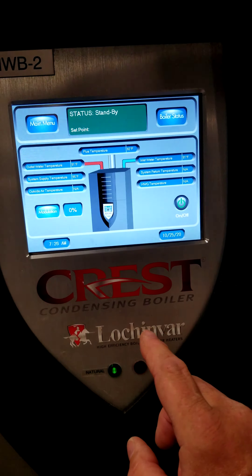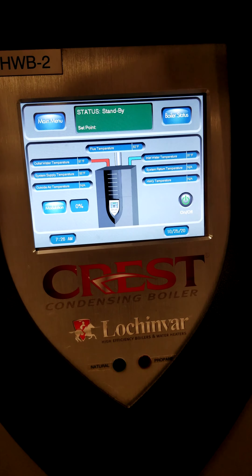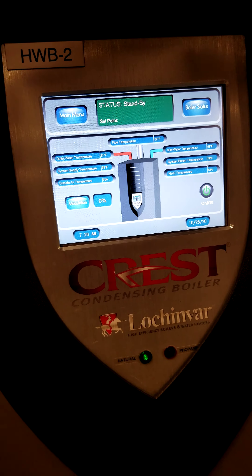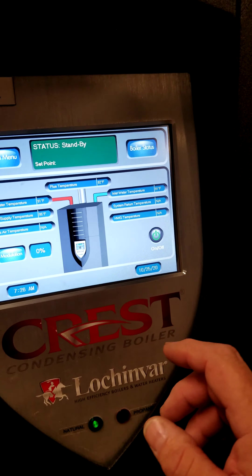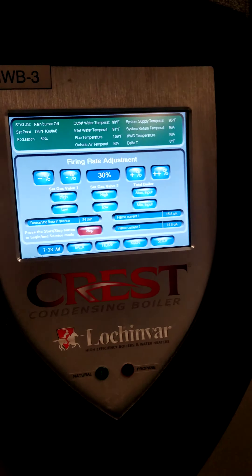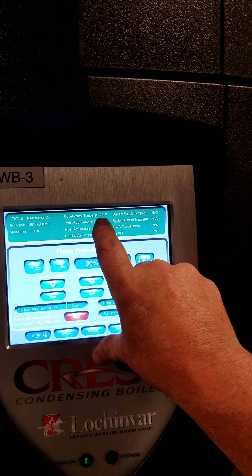Numbers one and two are going to try to start but they're going to fail because their blowers aren't sensing any static pressure. I'm going to have to go up on the roof. I did that late yesterday afternoon and cleared the snow off the vents, but I didn't look at the outlets close enough — I think they're probably steamed over or plugged.